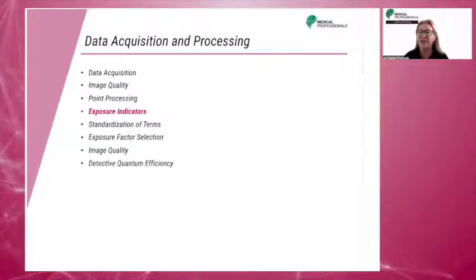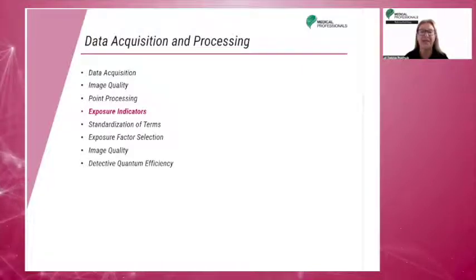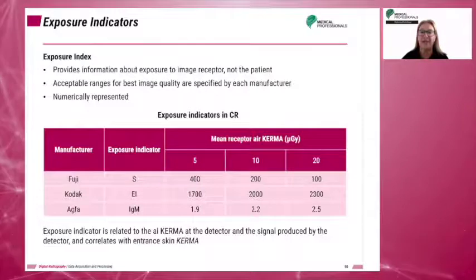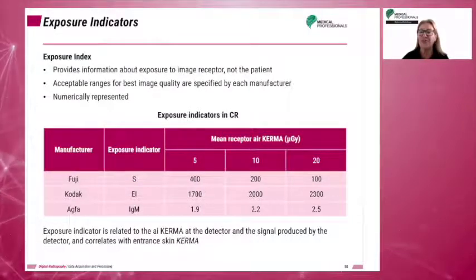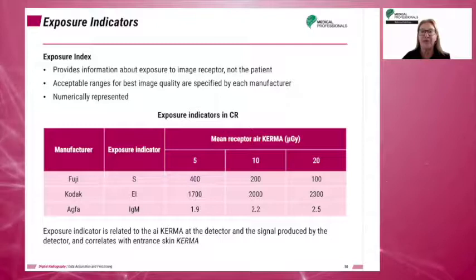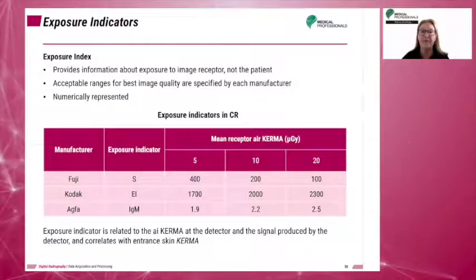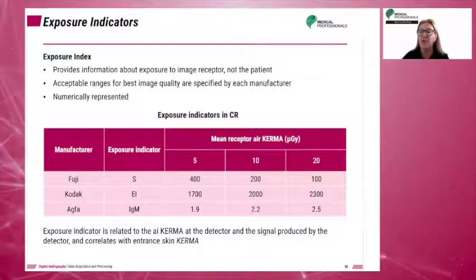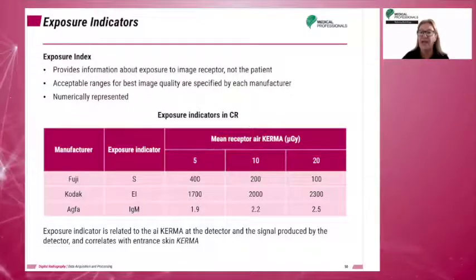In this section, we will cover the topic of exposure indicators. Exposure indicators are derived from the values of interest during histogram formation. It is important to remember that these numbers represent the exposure to the receptor and do not indicate the exposure received by the patient. Exposure indices can be affected by a number of factors having nothing to do with the technical factors used to obtain the image.